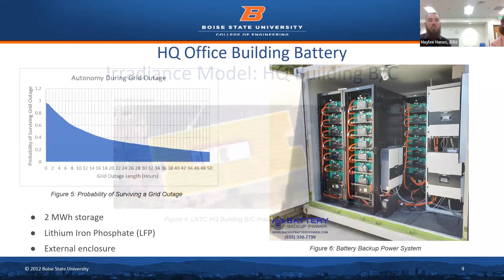And then for the second section of this design project, a battery energy storage system was added to the HQ building to help with voltage regulation, peak shaving, PV smoothing, and system resilience. We started by sizing the battery system using the NREL REopt online tool. Using the HQ building's energy use profile, we found a recommended battery size of 1.8 megawatt hours. However, to add some headroom and resilience, we opted to go with a 2 megawatt hour storage system.